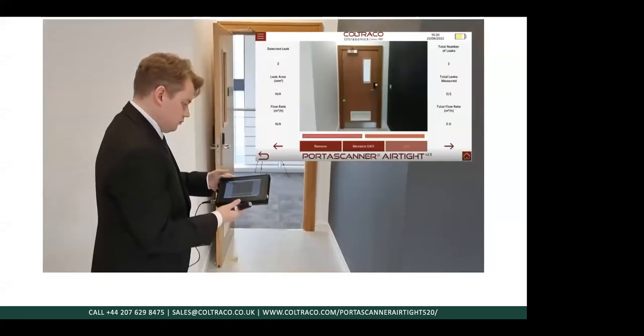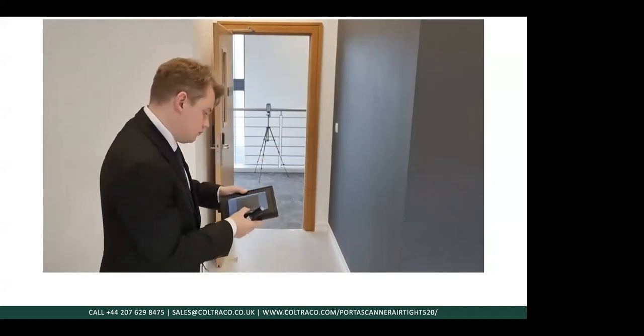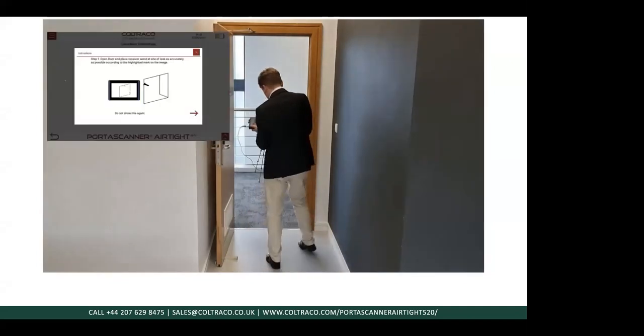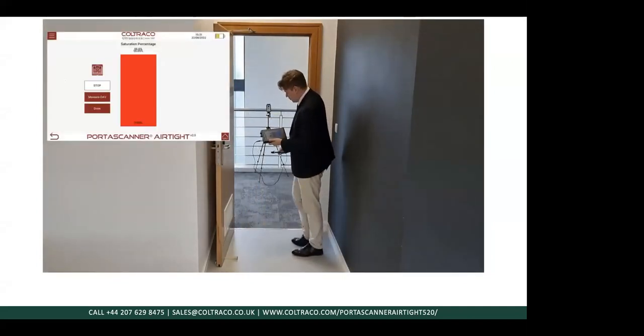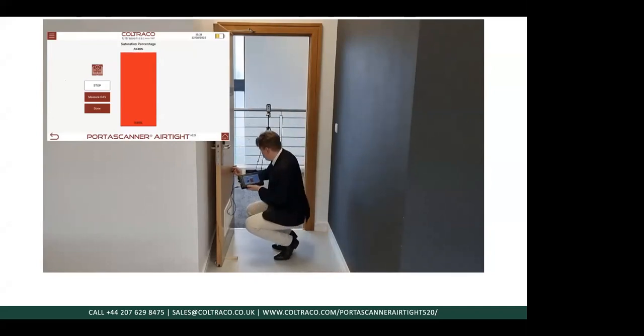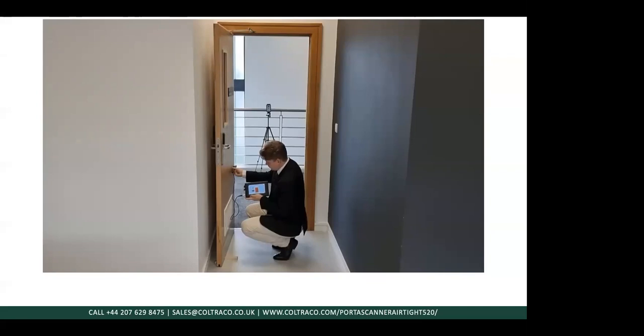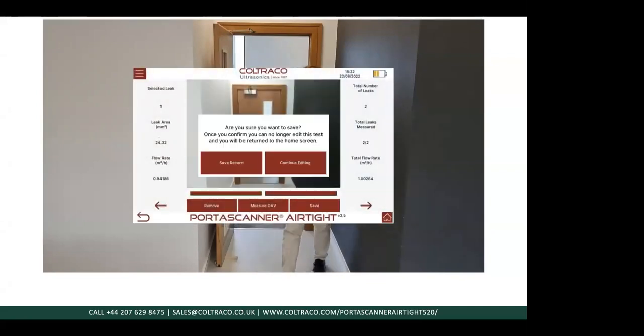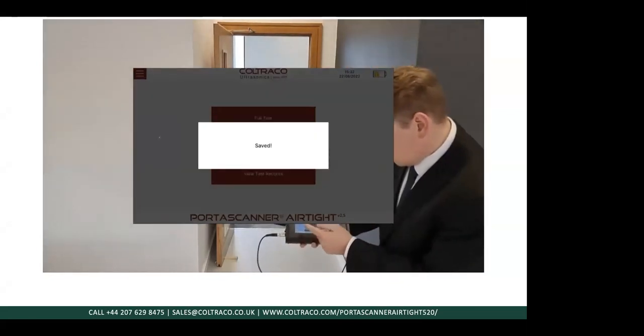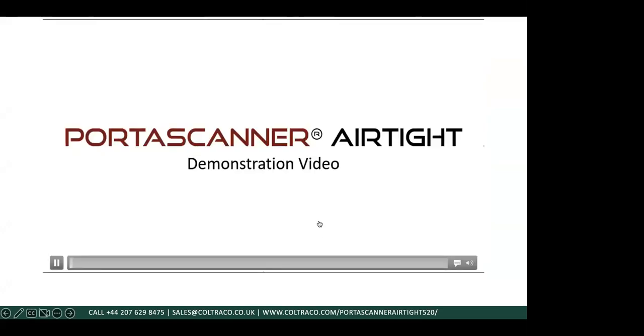He presses the Done button and takes a final measurement for each leak to determine the amplitude of ultrasound incident upon the far side of the door. This is called the open air value. The door is opened, the wand is placed in approximately the location that the leak was detected, and the measure button is pressed. Once Angus has done this for both of the leaks detected, the data for the leak location, sizes, flow rates, and air permeability may be saved by pressing the Save button.